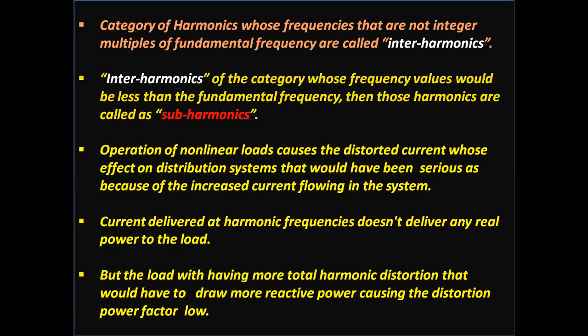Operation of nonlinear loads causes distorted current whose effect on distribution systems would be serious because of the increased current flowing in the system. Current delivered at harmonic frequencies does not deliver any real power to the load, but loads with higher total harmonic distortion draw more reactive power, causing the distortion power factor to be low.